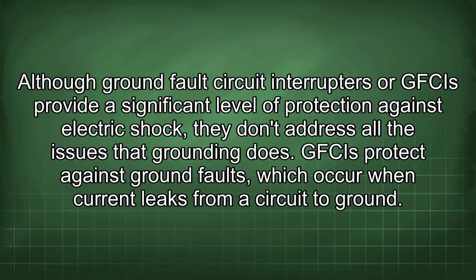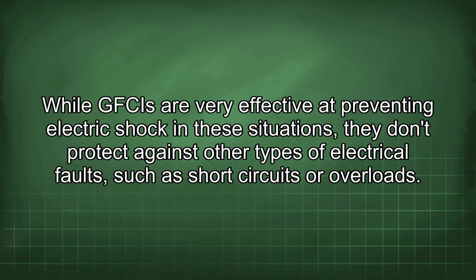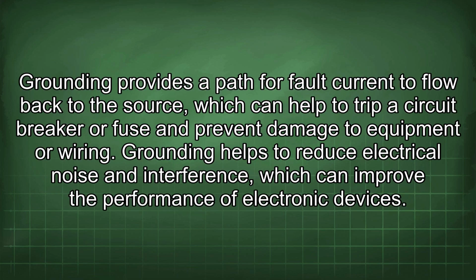GFCIs protect against ground faults, which occur when current leaks from a circuit to ground. While GFCIs are very effective at preventing electric shock in these situations, they don't protect against other types of electrical faults, such as short circuits or overloads. Grounding provides a path for fault current to flow back to the source, which can help to trip a circuit breaker or fuse and prevent damage to equipment or wiring.